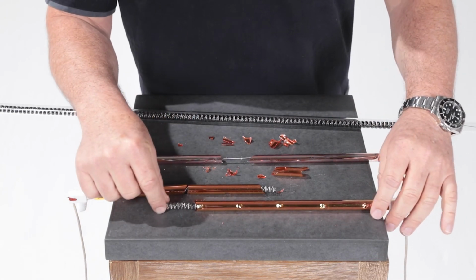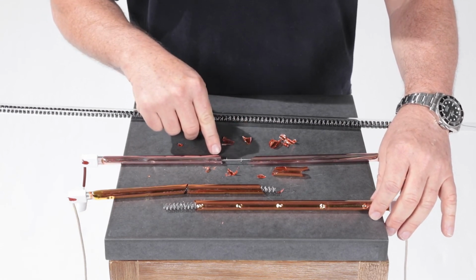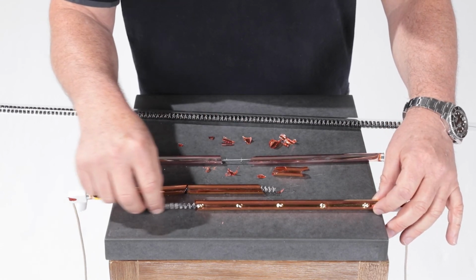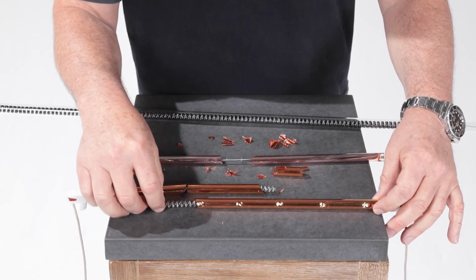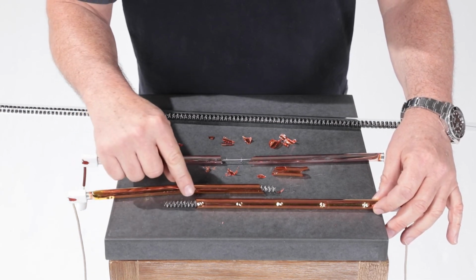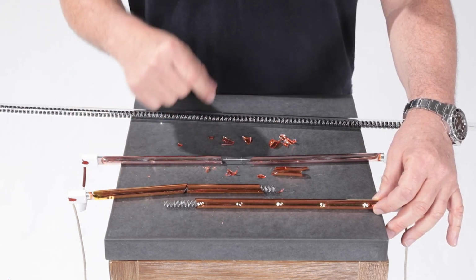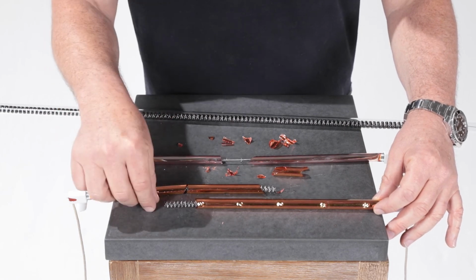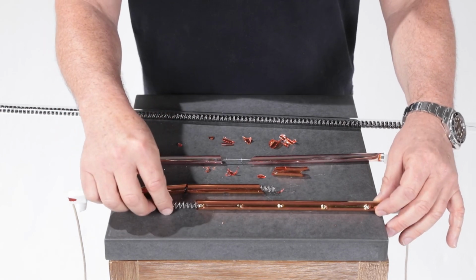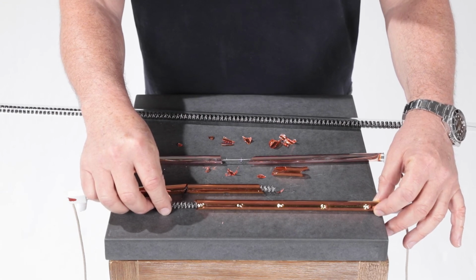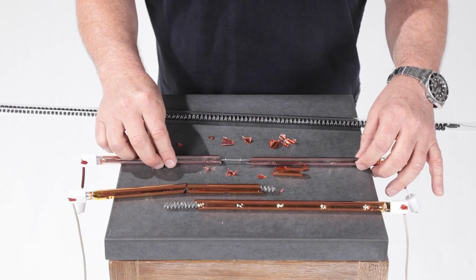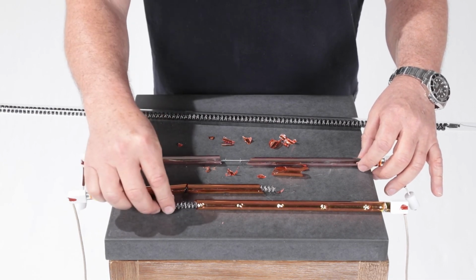The next thing to note is the actual way this brand new lamp, this is the ULG Plus lamp, has been formed. It's very, very different to the traditional thin line of tungsten. And what that does is it gives us a lot more stability with the core itself, which allows it to last longer. Because the heat and the light are being generated from a lot more wire rather than a thin line, it's also an awful lot dimmer, whilst giving out the same amount of heat. So this is a new generation of ULG Plus lamps. They're very, very low light, and this is our standard generation of ULG lamps. It's still ultra low glare, but nowhere near as ultra low glare as ULG Plus.